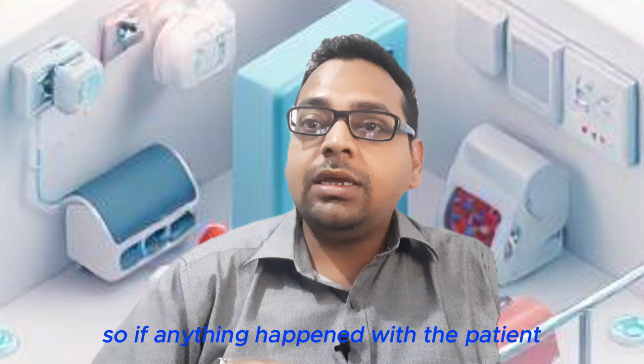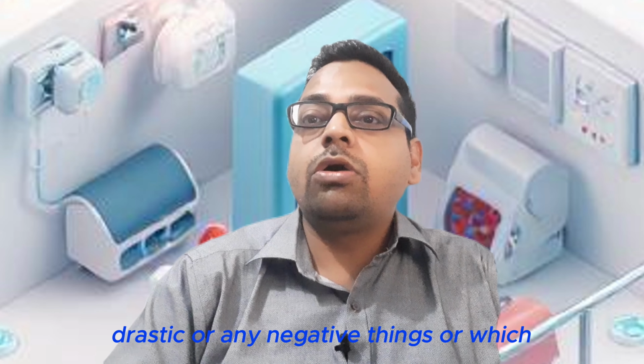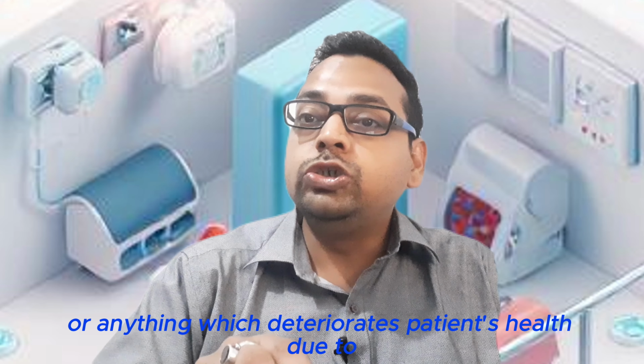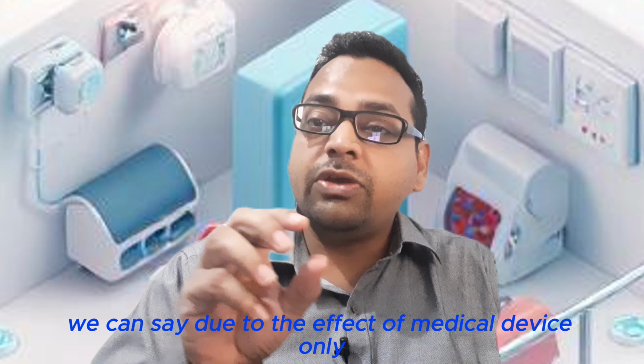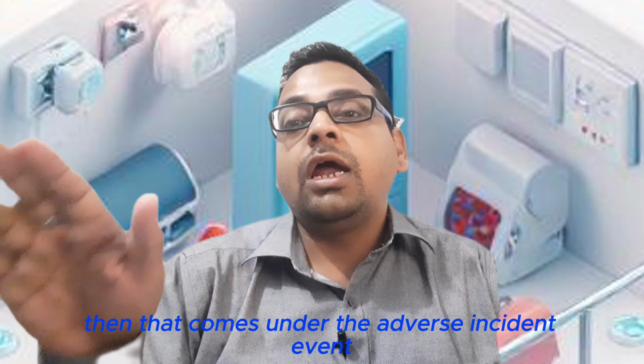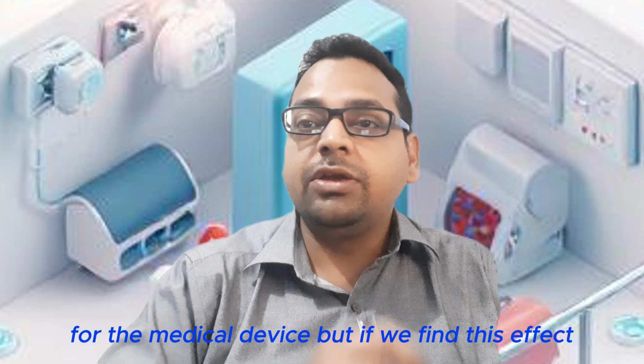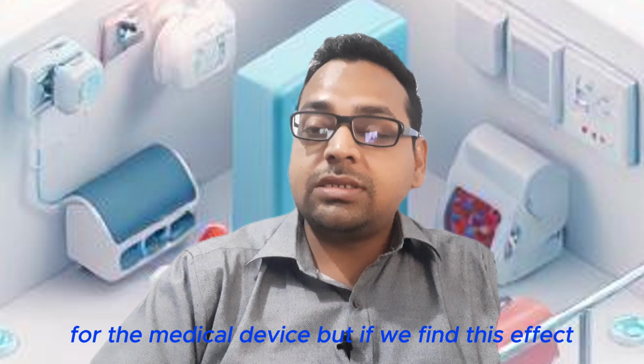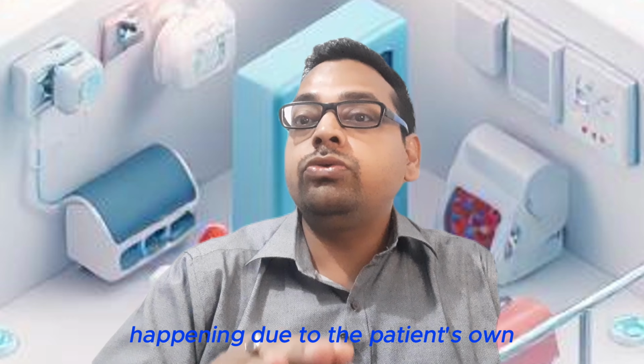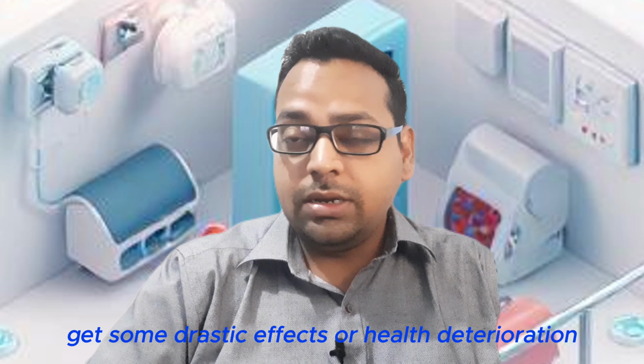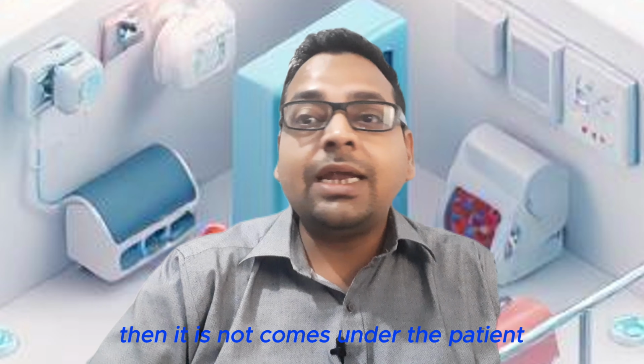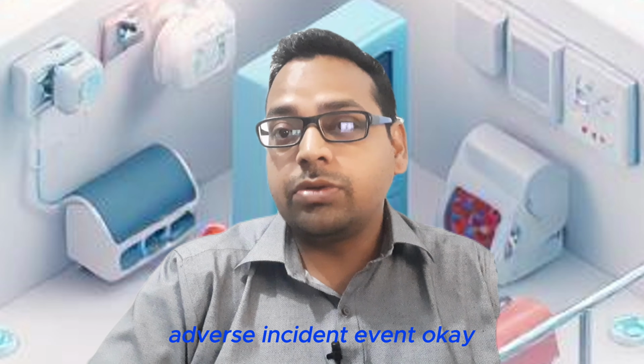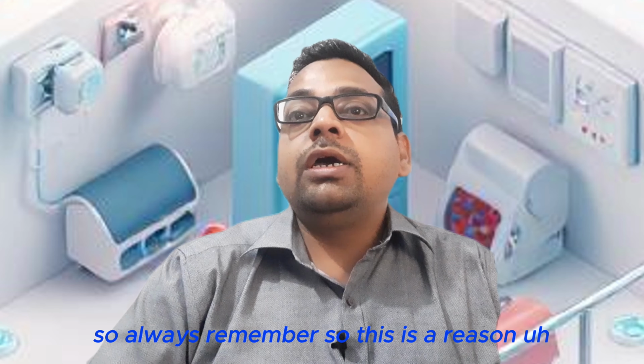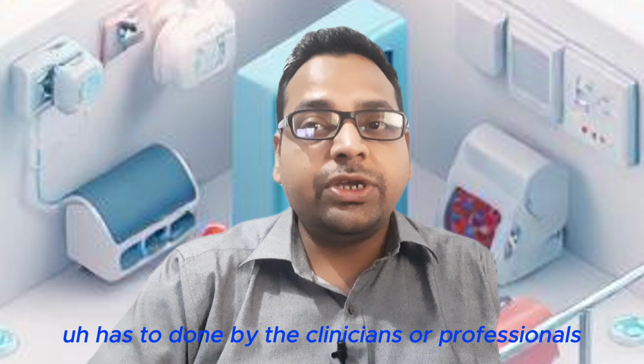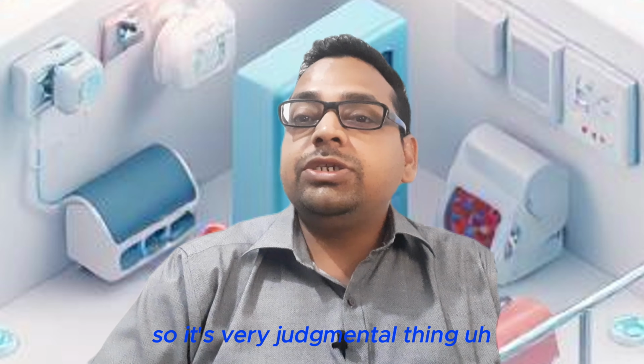So if anything drastic or negative happens with the patient, or anything which deteriorates the patient's health, due to, or very concretely we can say due to the effect of the medical device, only then does it come under the adverse incident event and get filed for the medical device. But if the effect or health deterioration happens due to the patient's own underlying or previous health situations, then it does not come under the adverse incident event. Always remember, this is the reason investigation has to be done by the clinicians or professionals operating on the patients. So it's a very judgmental thing.